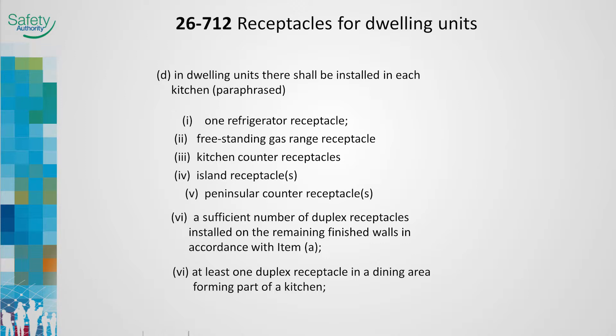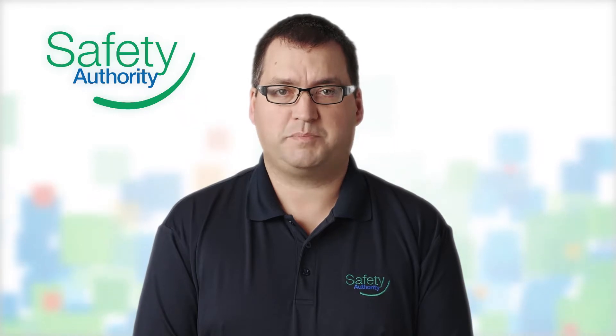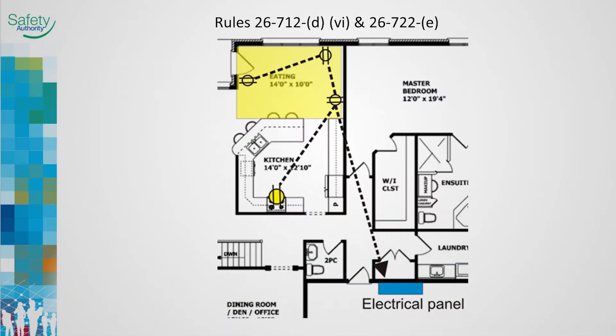The 2015 Code Rule 26-722E requires these new kitchen wall receptacles to be supplied by a dedicated circuit. The gas range receptacle may also be included. Rule 26-722E states that all receptacles on kitchen walls and the gas range receptacle must be on at least one dedicated circuit. Rule 26-712D6 now requires the receptacles installed in eating areas to be installed similar to outlet installations in other living areas, and Rule 26-722E requires these receptacles to be on a dedicated circuit.